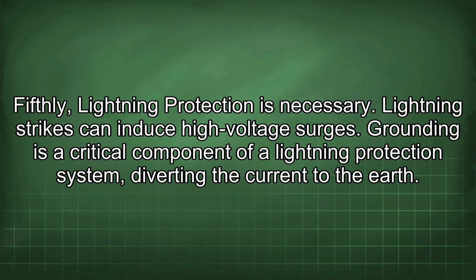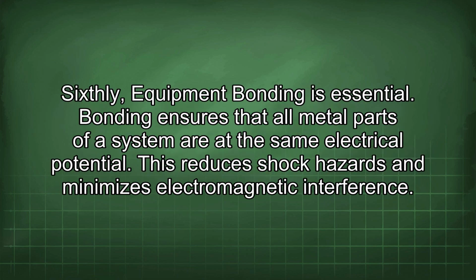Fifthly, lightning protection is necessary. Lightning strikes can induce high voltage surges. Grounding is a critical component of a lightning protection system, diverting the current to the earth. Sixthly, equipment bonding is essential. Bonding ensures that all metal parts of a system are at the same electrical potential. This reduces shock hazards and minimizes electromagnetic interference.